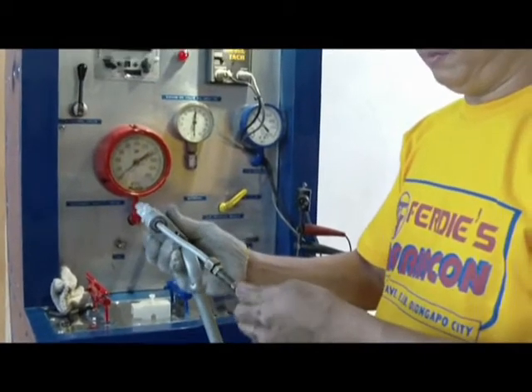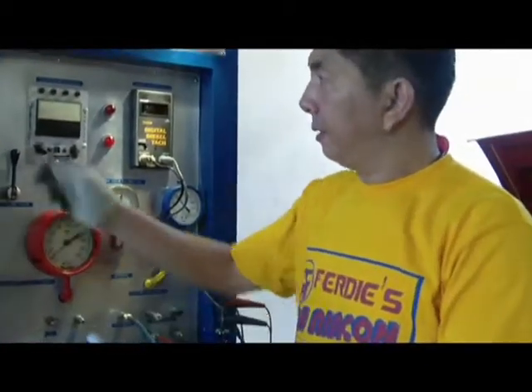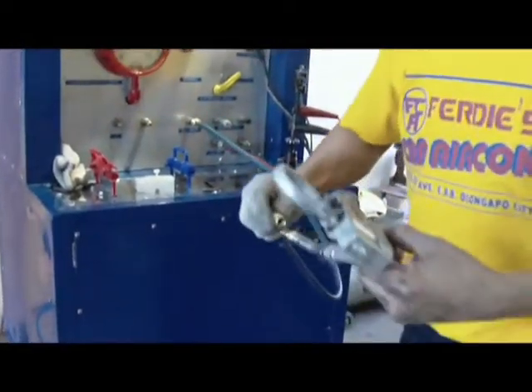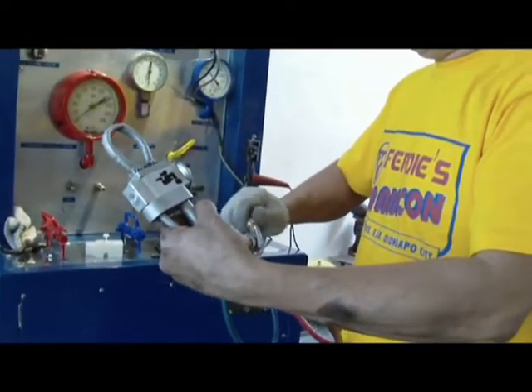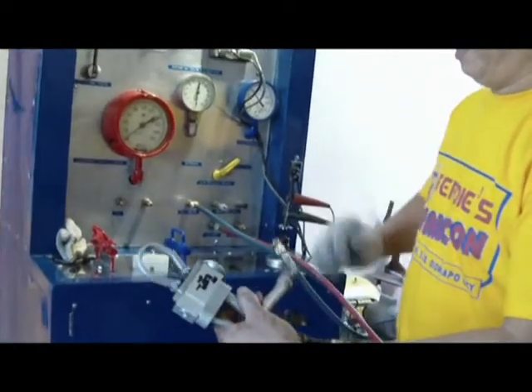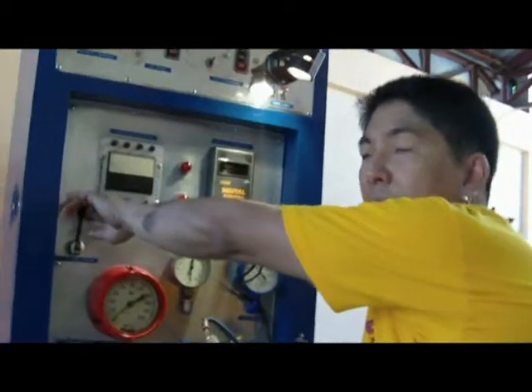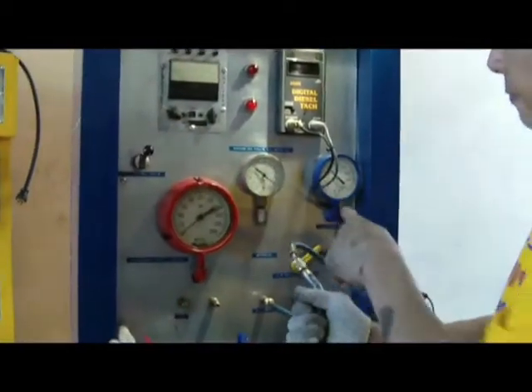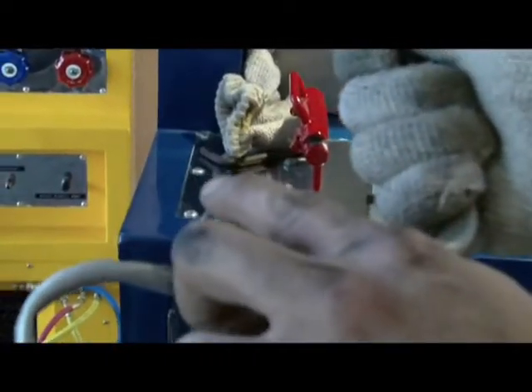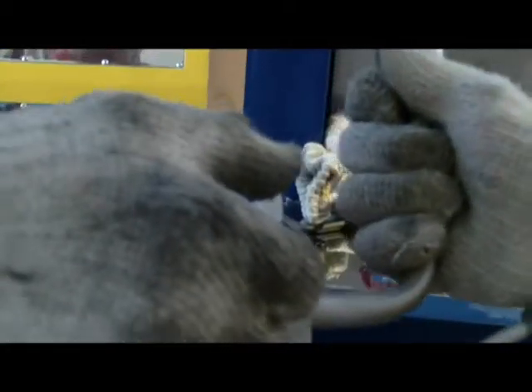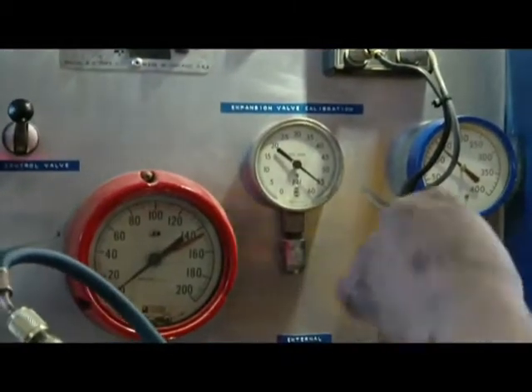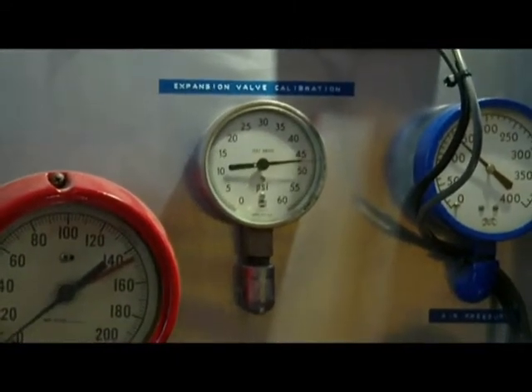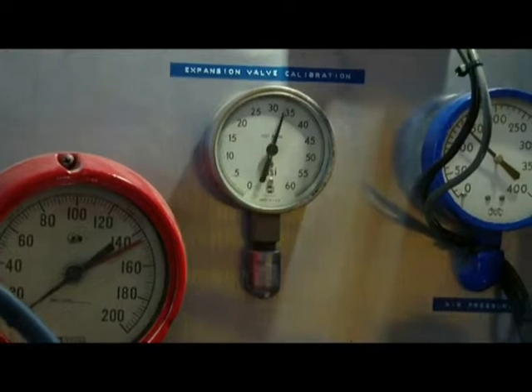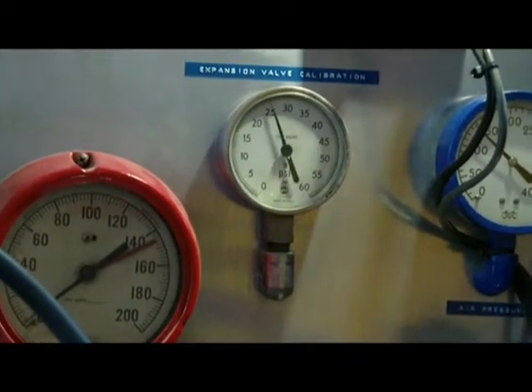First, check the pressure. The outside pressure here. At this point, I will open the air source and it will go high again. And this is the capillary tube wherein we will put a cold ice here. And this is the adjustment. So we'll try to put the cold, and you will see the reading here. That is the calibration of this expansion valve.